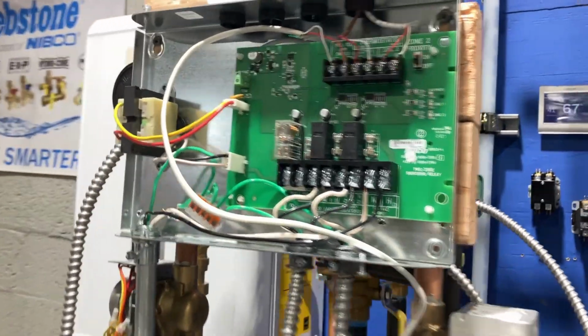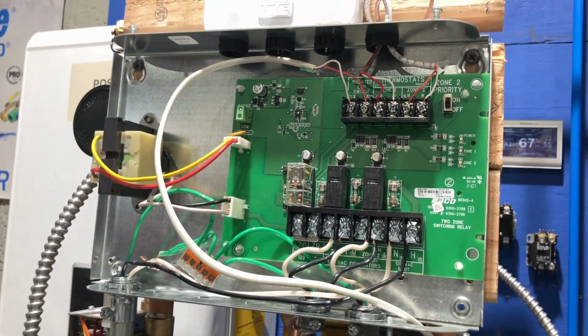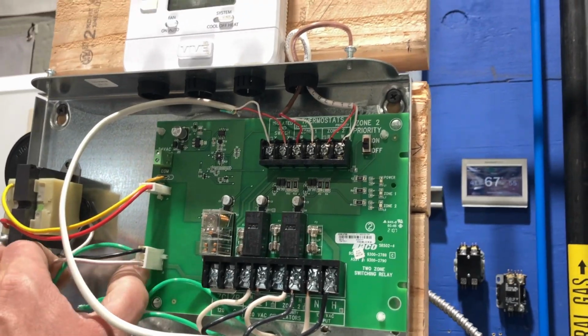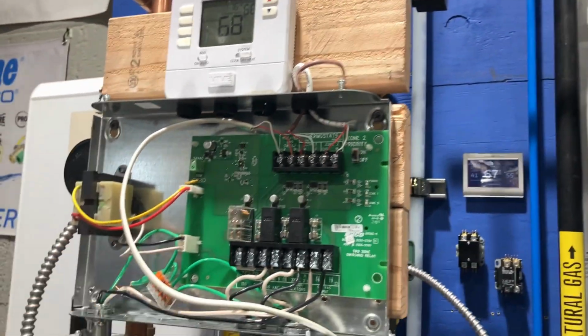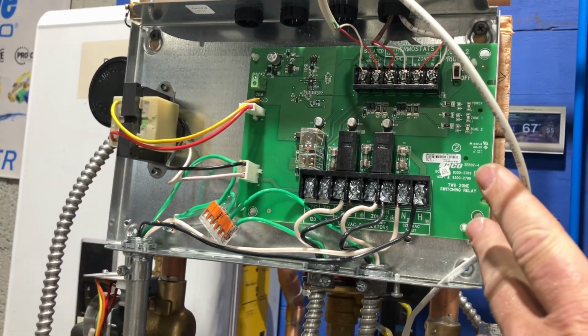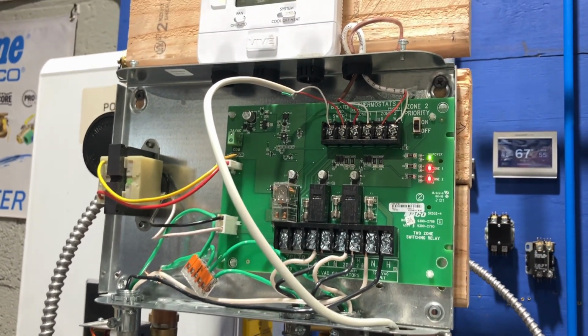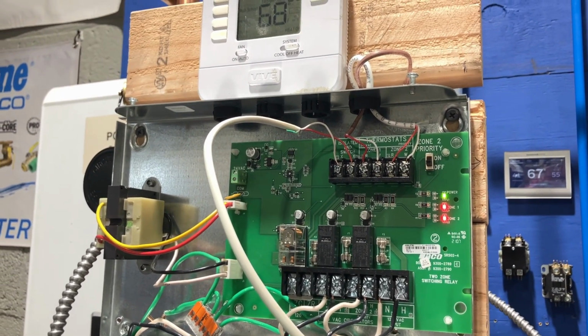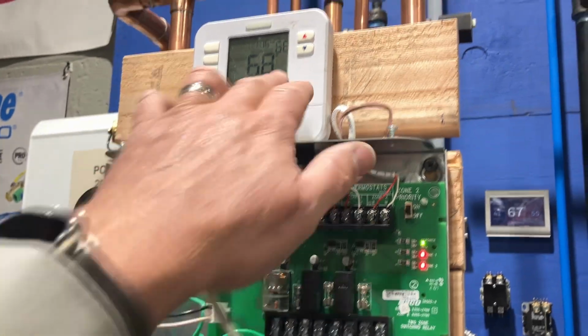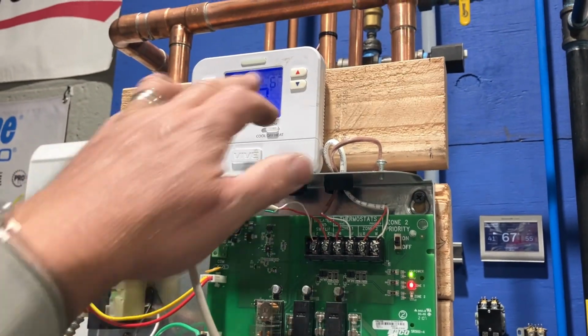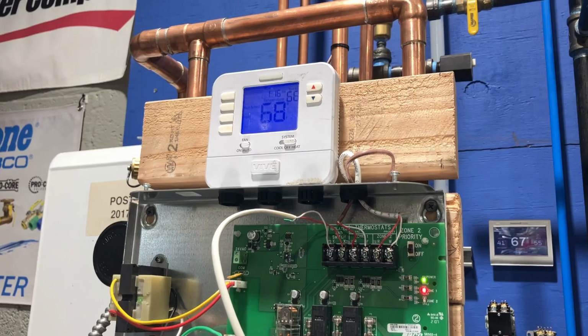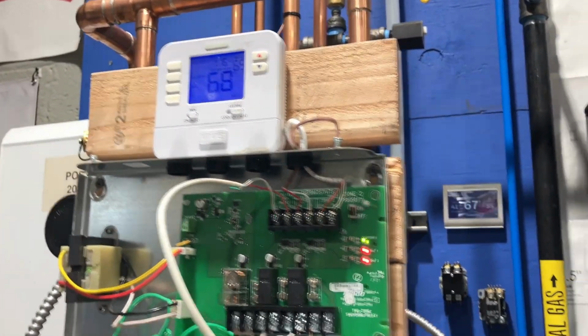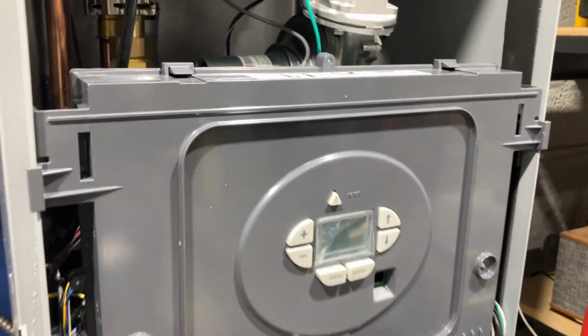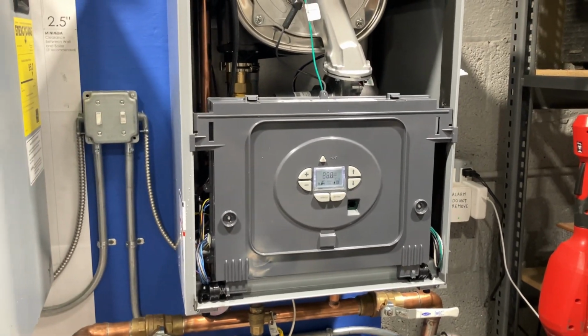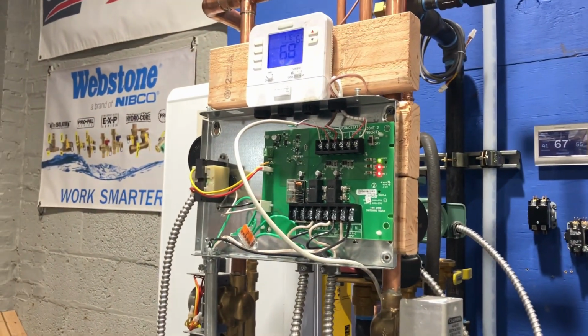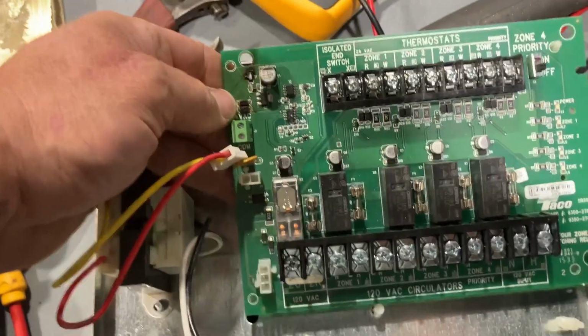All right, not the neatest looking of replacement relays, but nonetheless, everything is in there. Let's turn the power on. We have 2 zones actively calling right now. Yep, that works as well. Turn that back on. Good. Let's turn our boiler back on. Let that do a startup sequence. And then we'll make sure we're good to go.